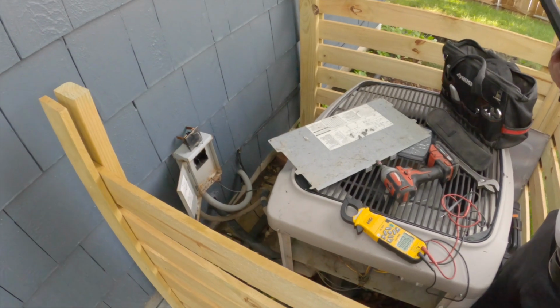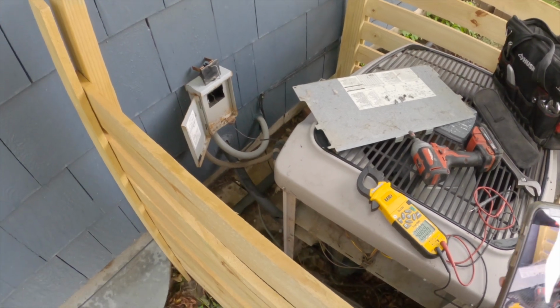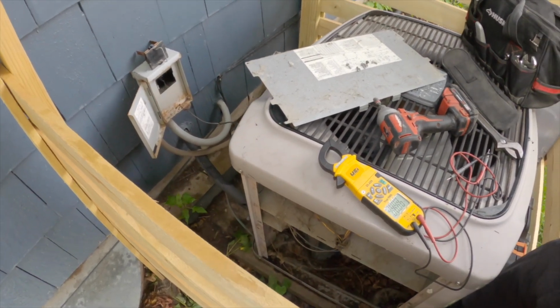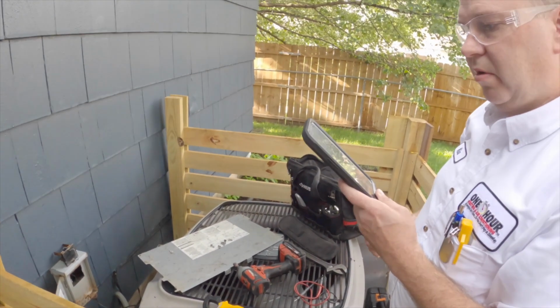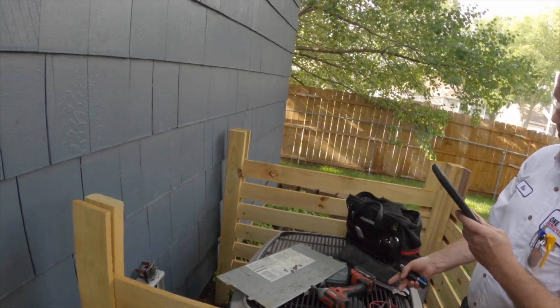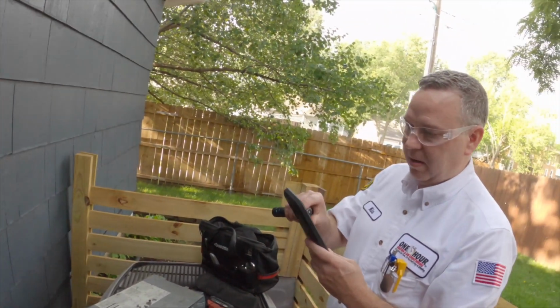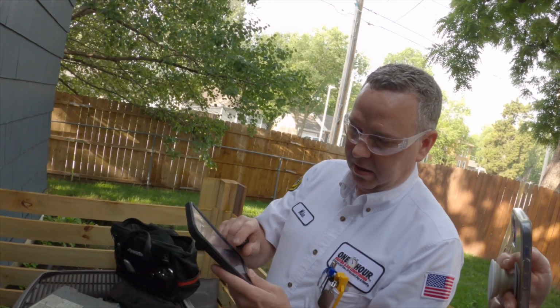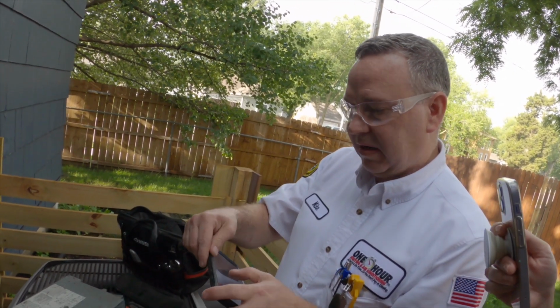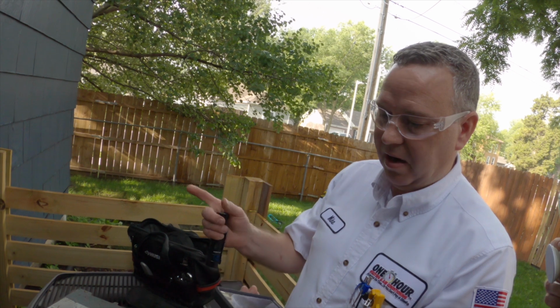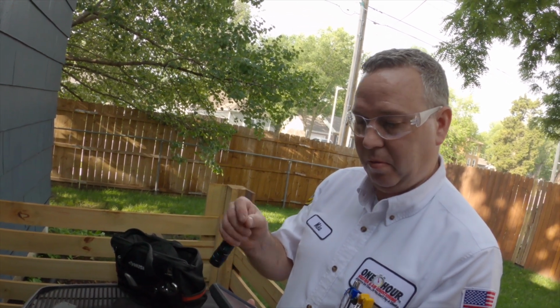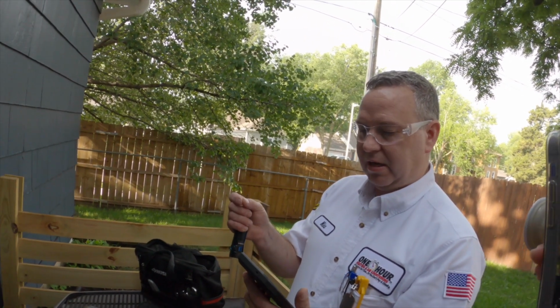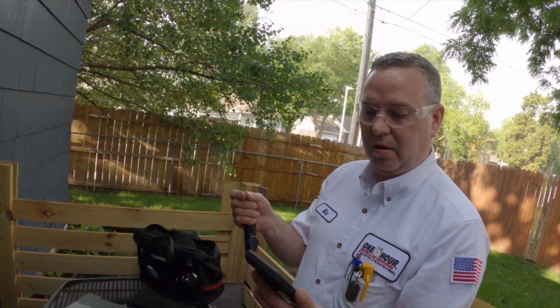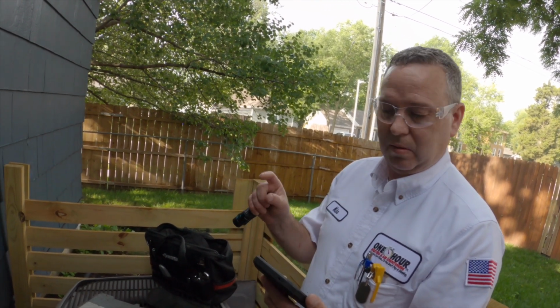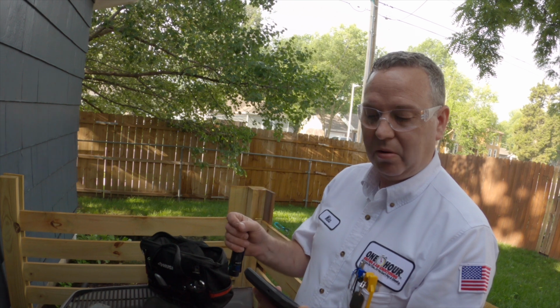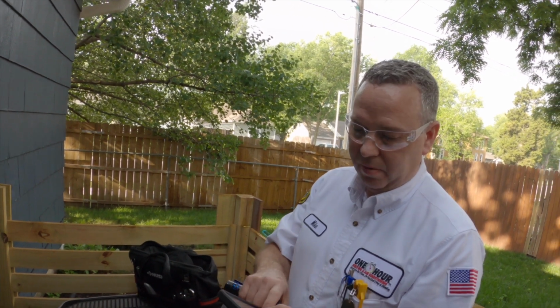You said contactor is charred? Yeah, the contactor is basically like a light switch for the system. Power goes to it and it tells the fan motor and the compressor to come on. But typically, every time it starts up and shuts off, it arcs. It gets to the point where it either welds those contacts shut, where the air conditioner will stay on and never shut off, or it can't make contact like it's supposed to and the air conditioner will never come on. This is getting pretty bad.